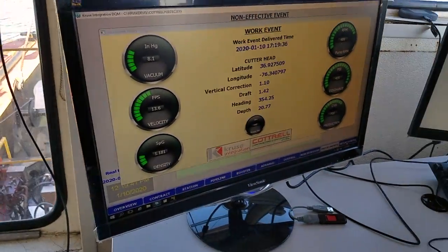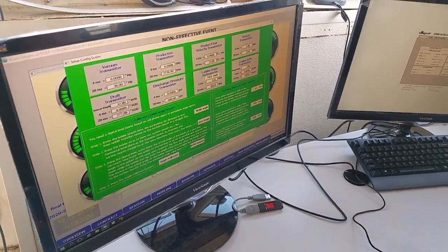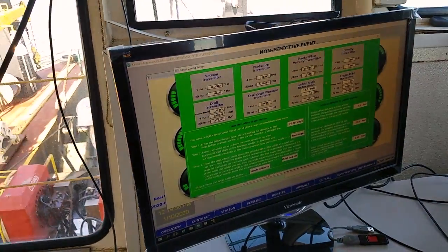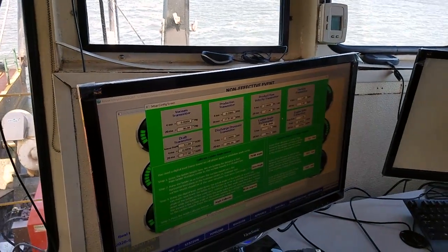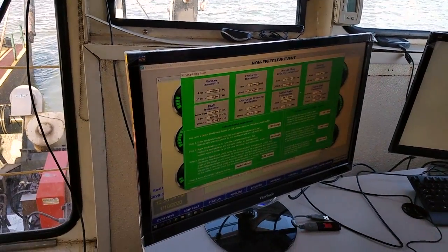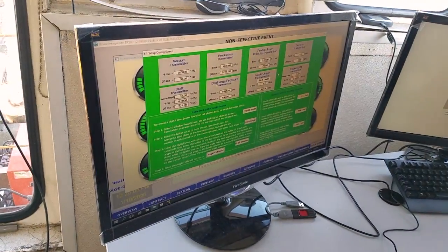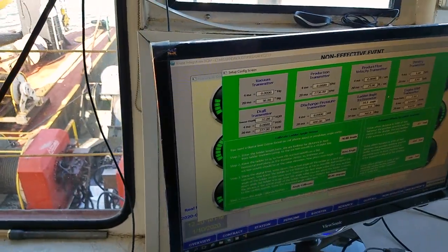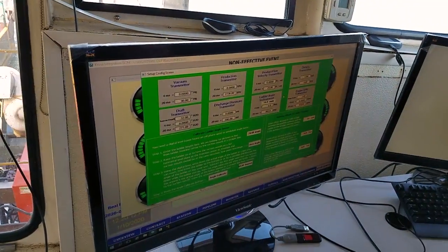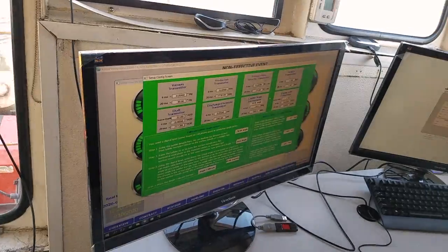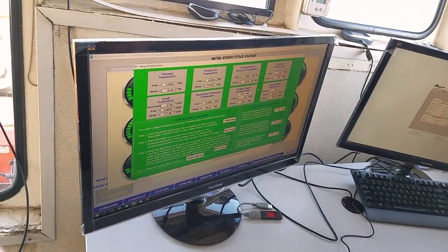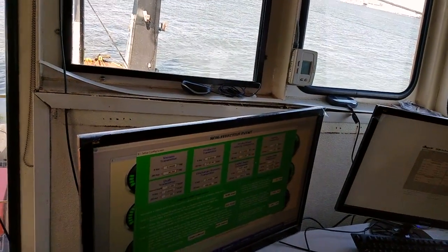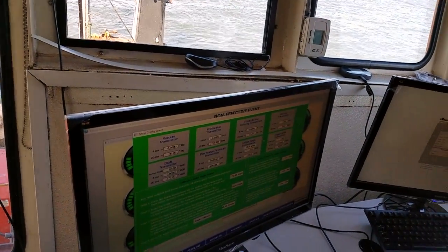So I run screen, which we already looked at. What's interesting here is typically you'd look at the tag on an instrument, and if it's 0 to 90 or something like that, it says on there, because they're all 4 to 20 milliamp transmitters. So you put in what's on the nameplate. But if you have something that goes negative and positive, for example negative 15 psi to vacuum and positive 60, that's actually 0 to 75.